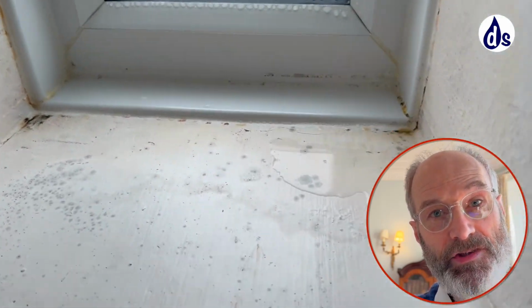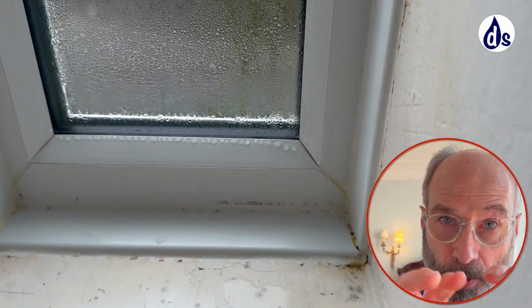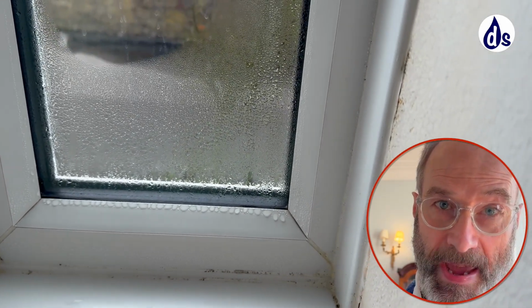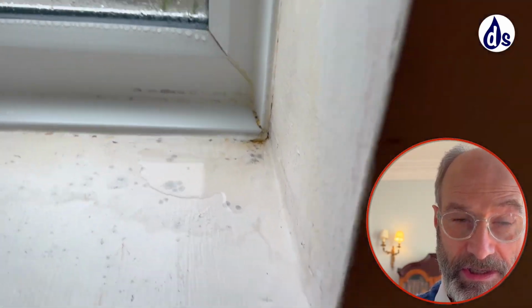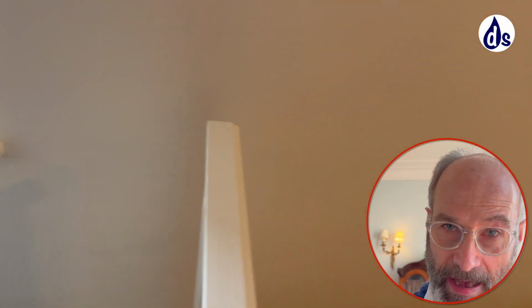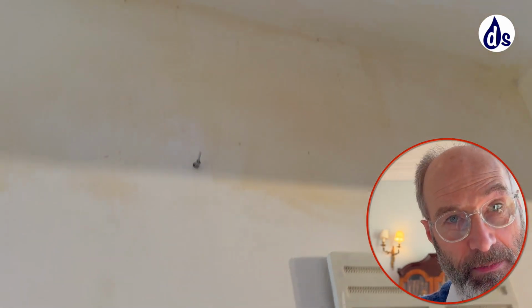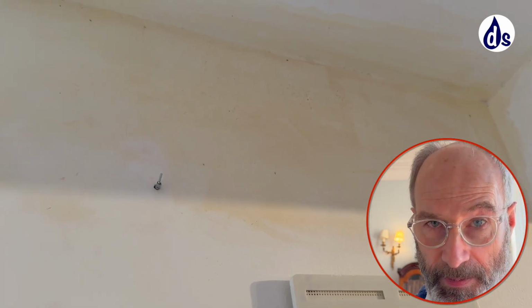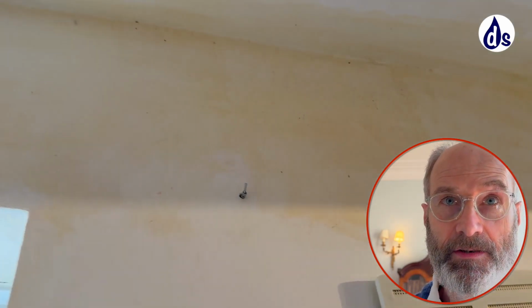Now, going back into the room itself, you can see there's poor airflow around the beds. This traps the humid air against the wall, increasing the risk of dampness, and there's mould as well. And you get mould where you get high surface relative humidity, over 85% for long periods of time.